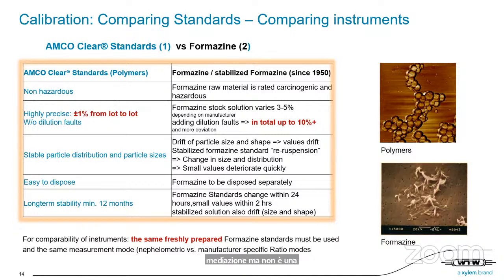And formazin raw materials are not very healthy. The formazin itself is not as bad as the raw material. And then also, depending on the raw material manufacturer, we already have a variation of 3 to 5% in formazin between different manufacturers. And if we make a stock solution, normally 4,000 NTU, it can already deteriorate after opening from 4,000 to 3,900, 3,700. And then we make a dilution. So actually, in formazin calibration instrument systems, a 10% plus tolerance in the system is normal.